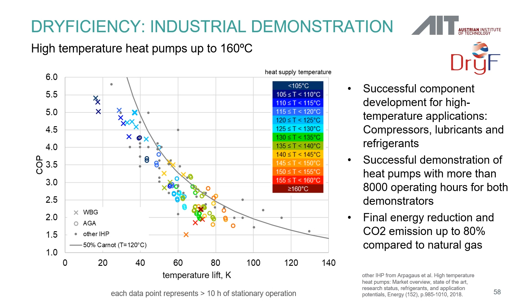Starting with the highest temperature, at 160 degrees, we had a COP of 2.2. When we compare this operation of the heat pump with a natural gas burner delivering the same amount of heat, we see a CO2 emission reduction of 62%.